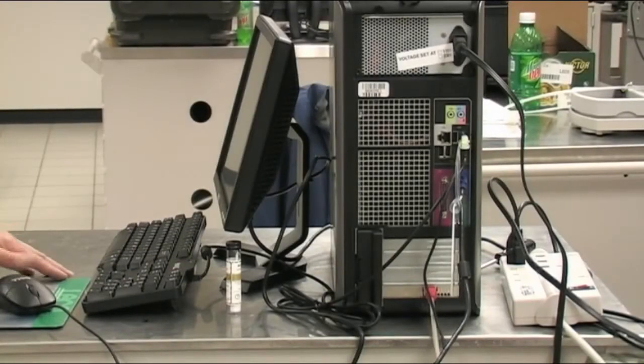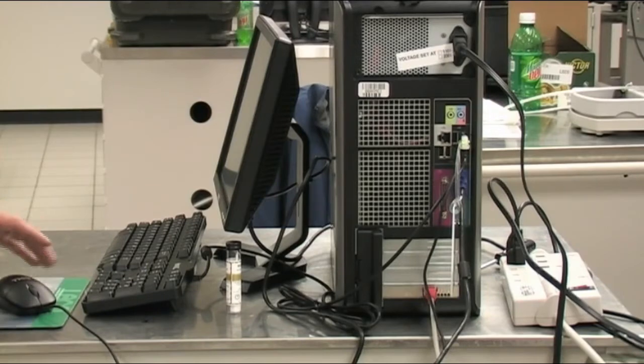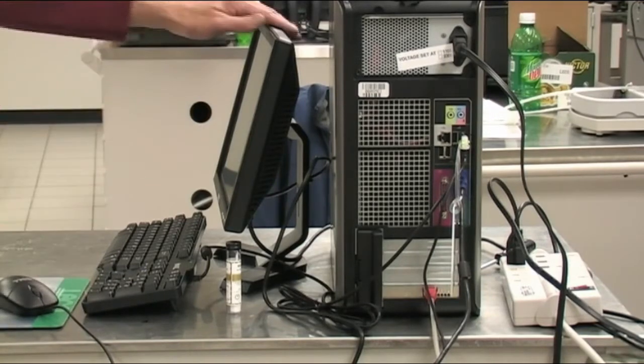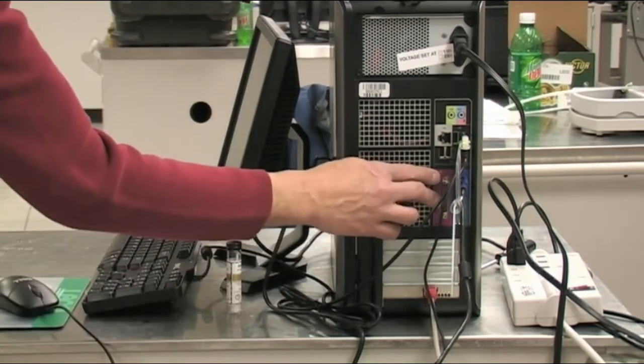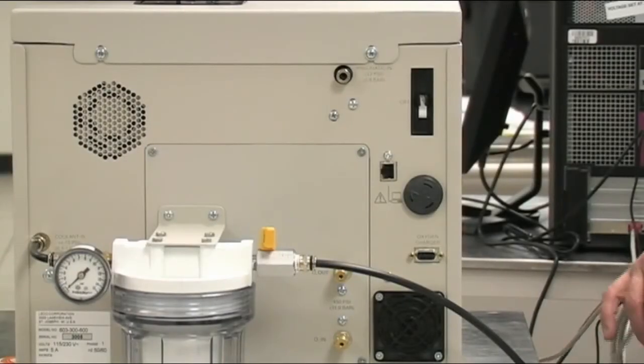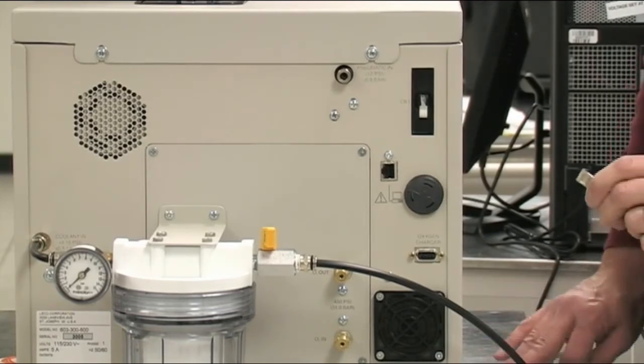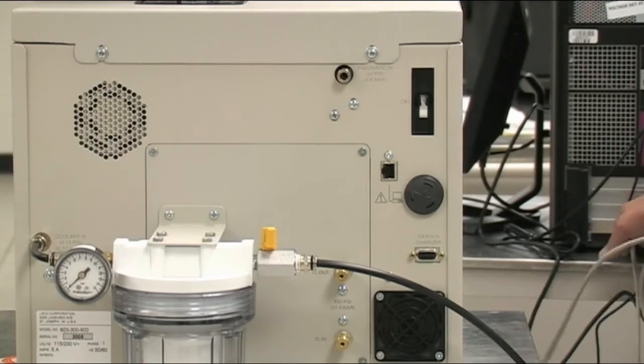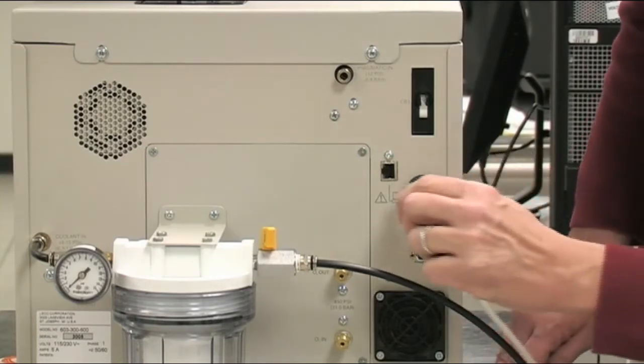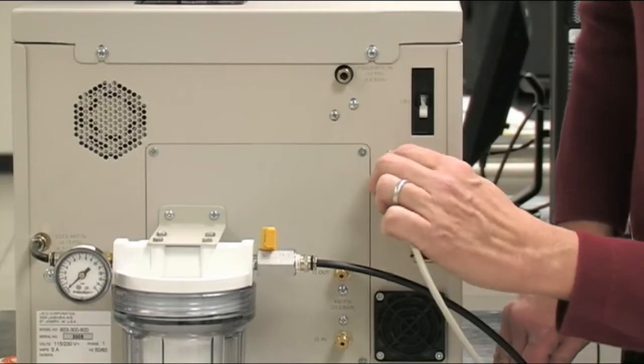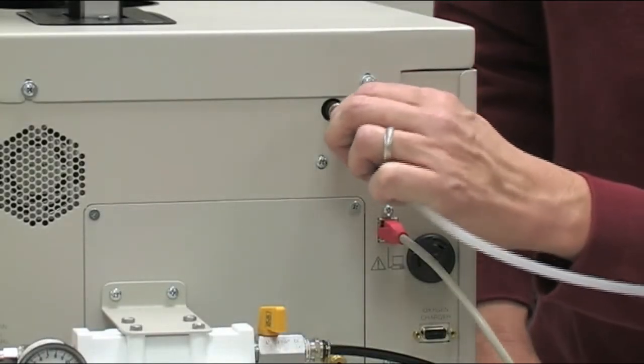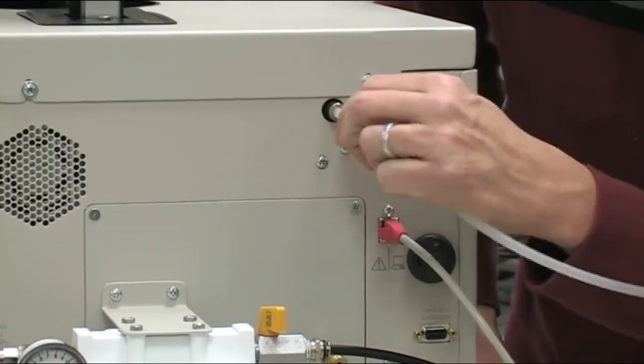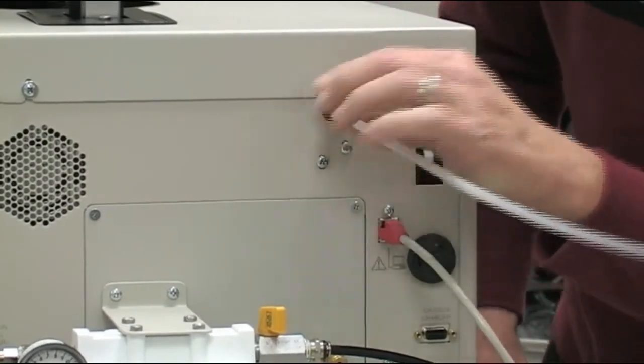Next thing you want to do is assemble the computer package. Make sure that you connect the mouse, the keyboard, and the monitor to the back of the computer. After assembling the computer with the keyboard, mouse, and monitor, you want to connect the Ethernet line from the computer, which is into the bottom Ethernet card, into the back of the instrument. Next thing you want to do is connect the pneumatic line. Your pneumatic pressure should be set at 12 psi.